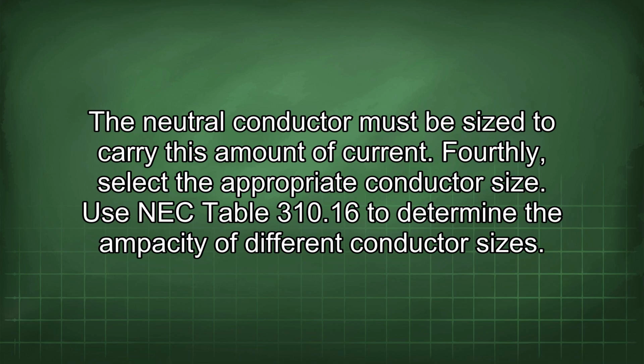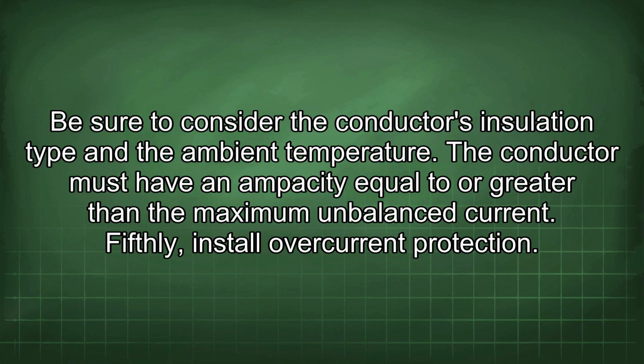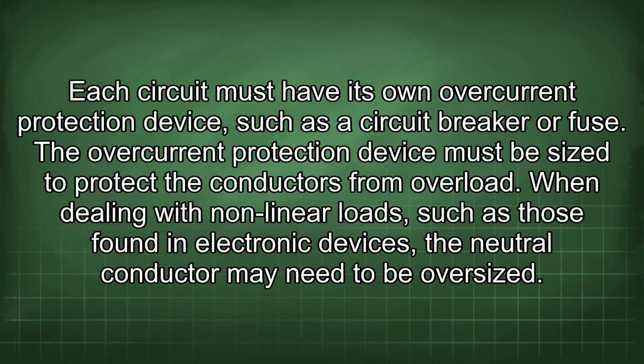Fourthly, select the appropriate conductor size. Use NEC Table 310.16 to determine the ampacity of different conductor sizes. Be sure to consider the conductor's insulation type and the ambient temperature. The conductor must have an ampacity equal to or greater than the maximum unbalanced current. Fifthly, install overcurrent protection. Each circuit must have its own overcurrent protection device, such as a circuit breaker or fuse. The overcurrent protection device must be sized to protect the conductors from overload.